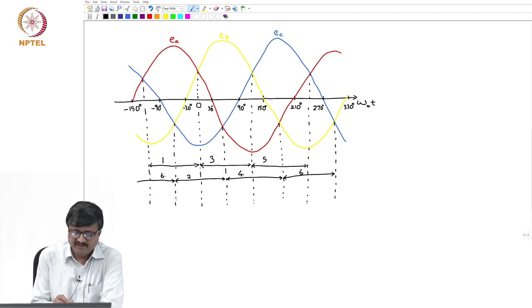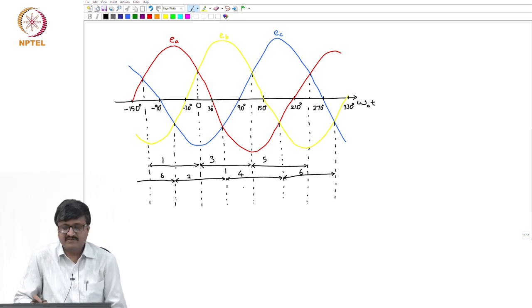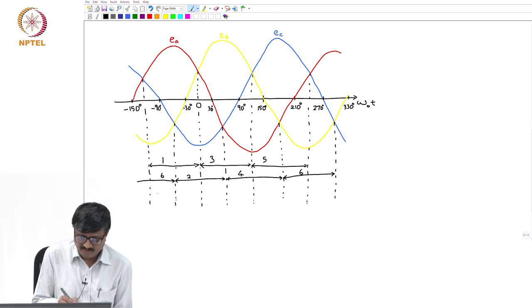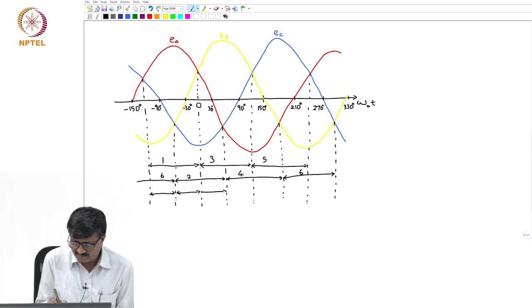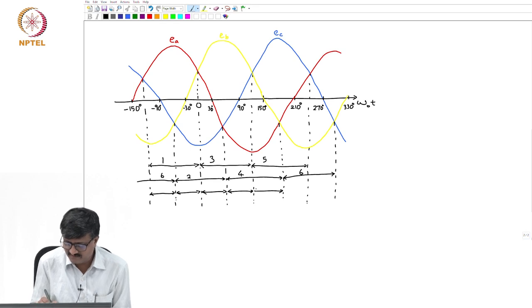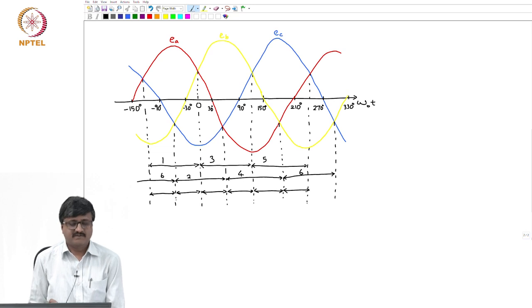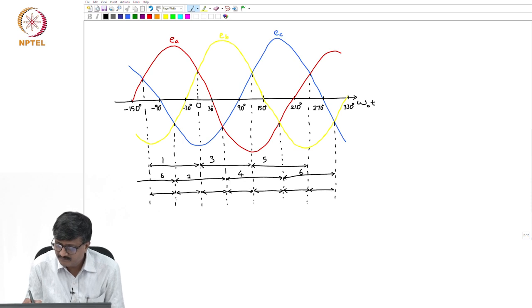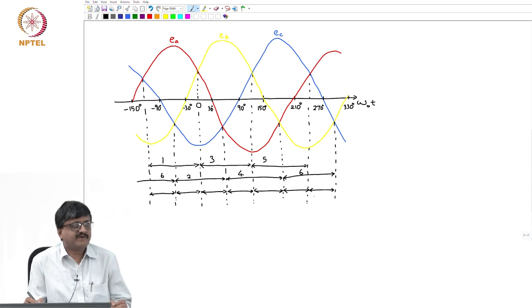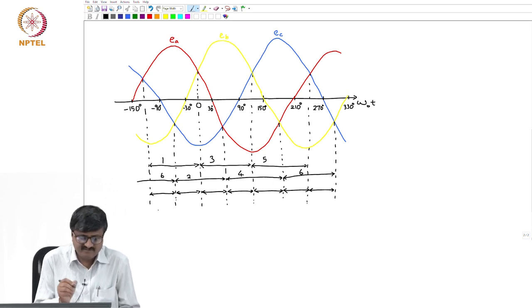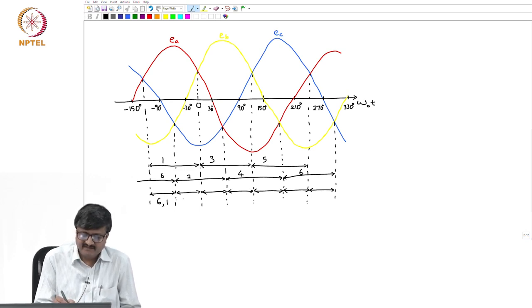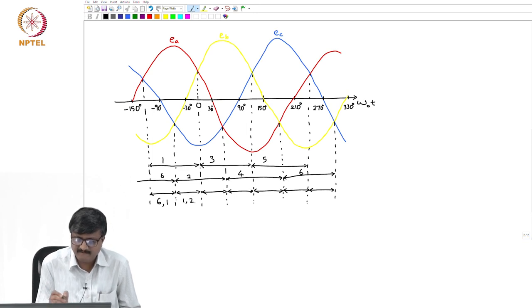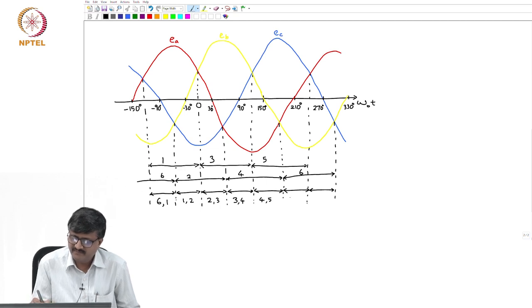We have now covered one cycle for the lower commutation group as well. We will consider intervals of length 60 degrees. At any instant one thyristor valve in the upper commutation group and one in the lower commutation group conducts. In the first 60-degree interval it is 6 and 1, then 1 and 2, then 2 and 3, then 3 and 4, then 4 and 5, then 5 and 6.